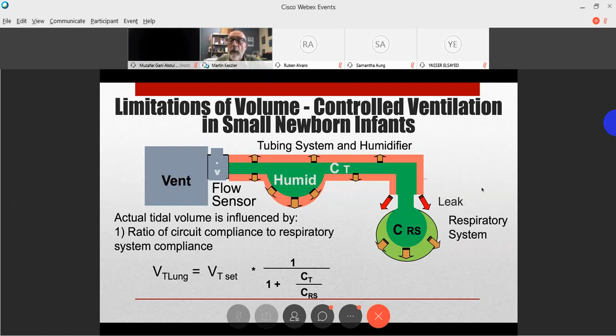or pressure-limited ventilation, which in its basic functionality is nothing more than a mechanical T-piece. And during the expiratory phase, if you're talking about some sort of an intermittent mandatory ventilation approach, the expiratory valve is open, there's a circuit flow, there's a PEEP valve maintaining some distending pressure, and the patient can breathe in and out of the circuit. And when this ventilator cycles on, the expiratory valve closes, the circuit's pressurized, and gas enters the patient's lungs in proportion to the pressure within the circuit and the compliance of the lungs.